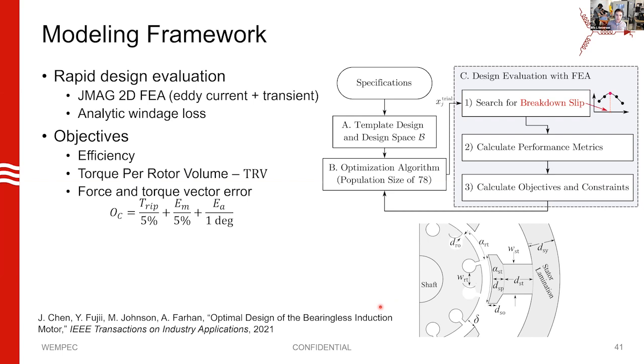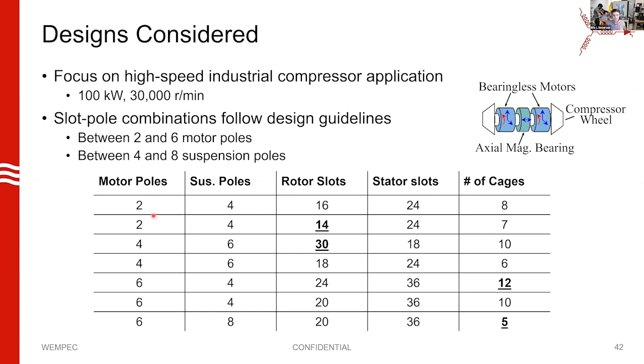We wanted to know how good of a job we could do designing a machine with one of these rotors. We developed an optimization framework that optimizes machines based on efficiency, rotor volume, and force vector error. We tried seven different slot-pole combinations, from two motor poles up to six, and four suspension poles up to eight, following best practices. We did this for an industrial compressor system of 100 kilowatts and 30,000 RPM, assuming two motor segments sandwiching axial bearings, so each motor segment is 50 kilowatts.